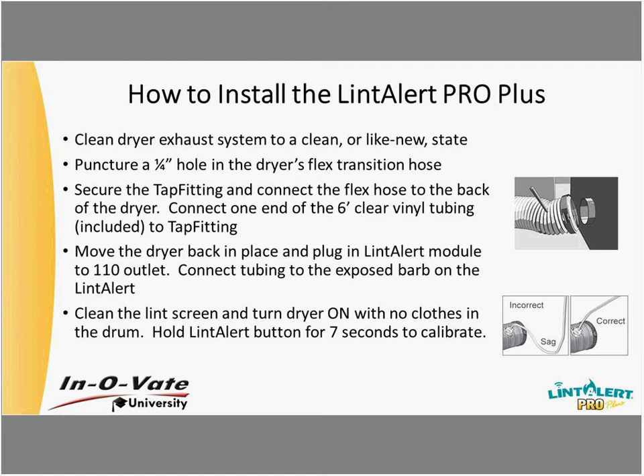The 6 feet of vinyl tubing that it comes with—if you end up with a little bit of excess, as you see bending or sagging at the bottom in that image, we do ask that you simply cut off the excess foot and a half or whatever it may be. In doing so, you're eliminating the chance for lint to accumulate in that clear plastic, and also eliminating the chance for condensation to build up in there. Again, that's just an effort to get continuous clean readings with the product and avoid any functionality issues.